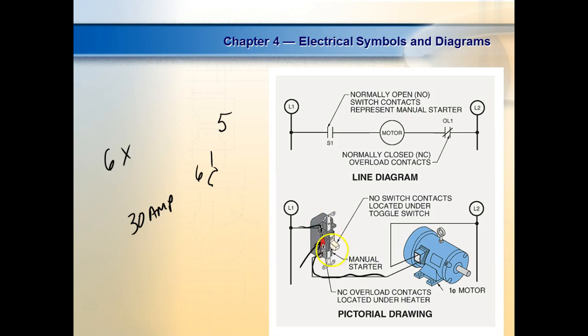So what happens is that if I turn it on and the motor doesn't start, this thing right here will open up the motor circuit, even if the switch is what? Even if the switch is on. Most of your overloads have a reset button on them, so they don't reset automatically, and you literally have to push it in to reset it. I was looking for a motor starter with it, but we'll look at those later.